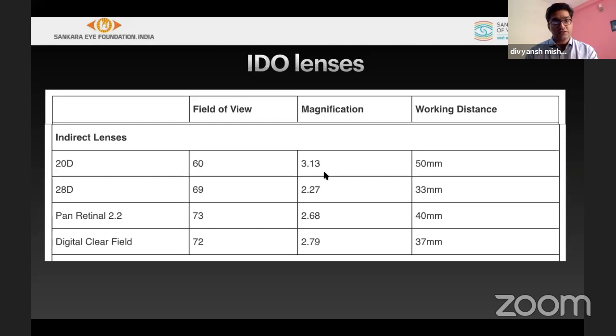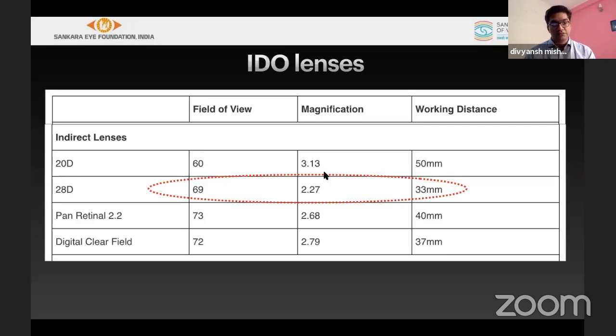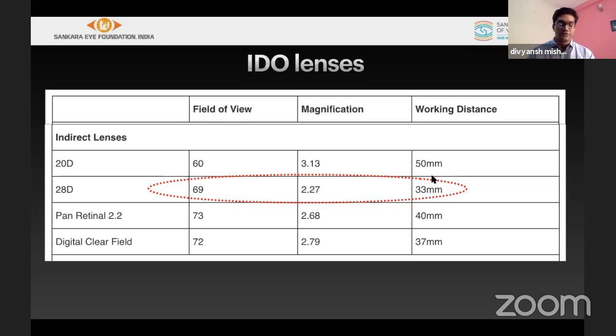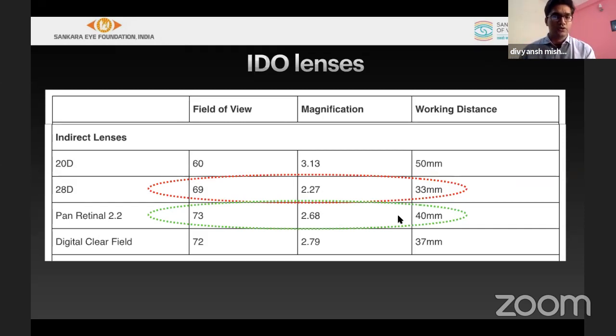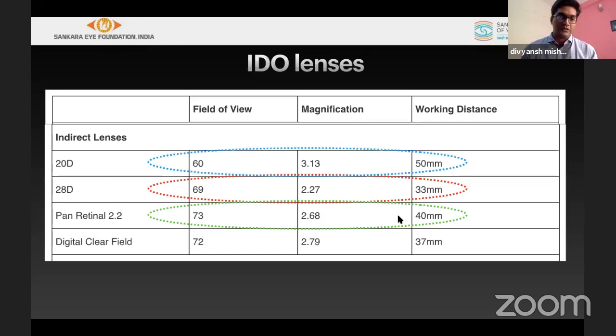Regarding lens selection for ROP, the ideal lens is a 28-diopter lens with a wider field of view, lesser magnification, and shorter working distance. The 2.2 lens has similar magnification and field of view with slightly better working distance. If neither 28D nor 2.2 is available, a 20D lens can be used.